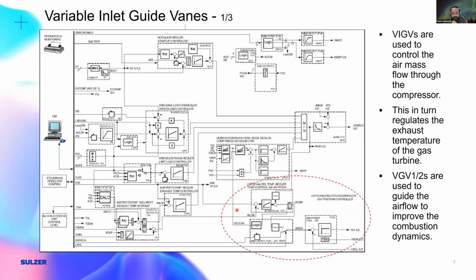And depending on the control, like whether it's a PI controller or a PID controller, you would have either open loop systems or closed loop systems. In this case, you can operate the IGV either in a closed loop, where you're taking the exhaust temperature as an input, let's say, measurement, which you want to maintain, or you could actually open it over a step controller, literally an open loop. For example, you might want to open the IGVs when you perform something you would call a compressor wash. If your compressor starts to foul, it means the performance is decreasing. You have a lot of dirt and debris sticking onto the blades, and then you typically go through a process where detergent is injected in, and you'd need to open or position the inlet guide vanes such that you'll be able to ingress to the last stage of the compressor.